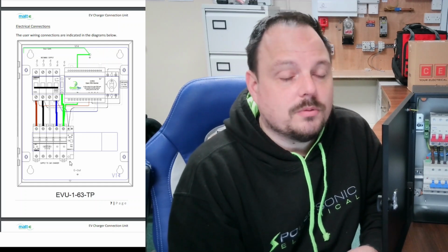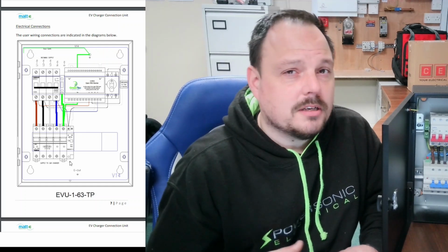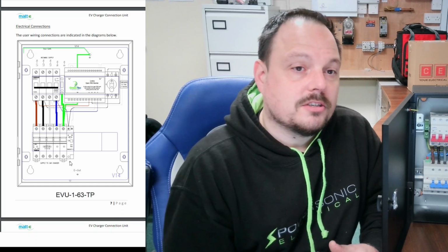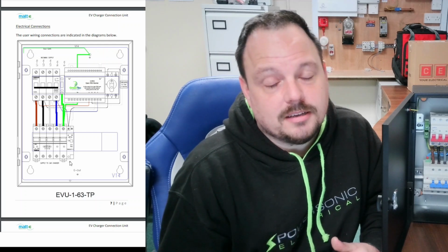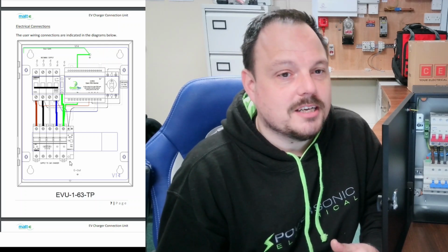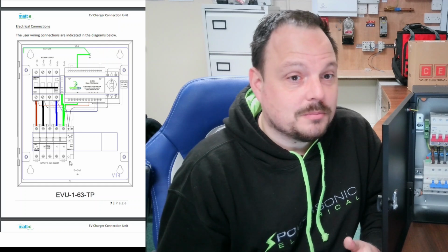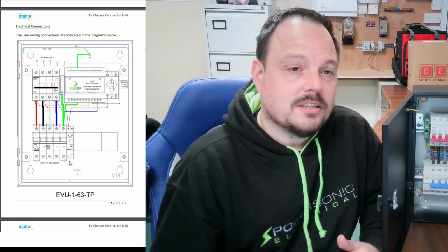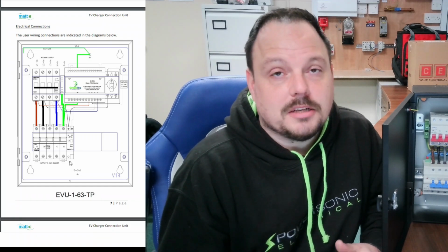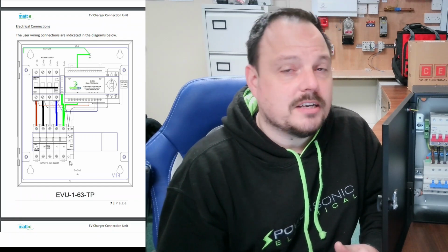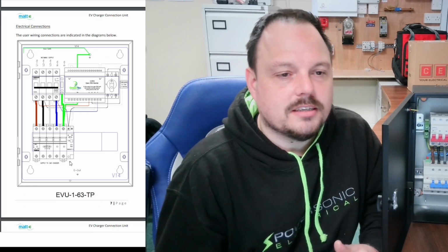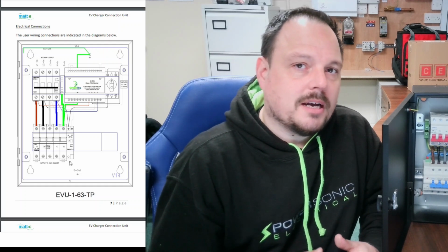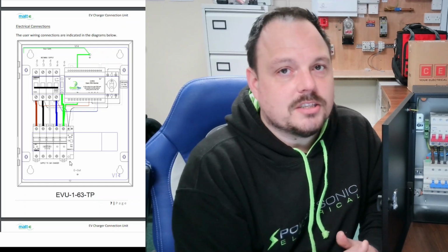If you are using a steel wire armor, some people connect the armor in at the load end, so if the earth opens, this is going to disconnect the earthing on that steel wire armor cable. That's an option that's available to you if you wanted. My preference is to connect the armor into the Matt-E itself and then make sure they are isolated from the charge point at the load end if you were using steel wire armor. And the reason for that is it then remains part of the electrical system internal to the installation.